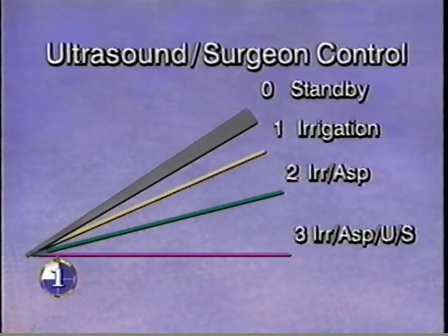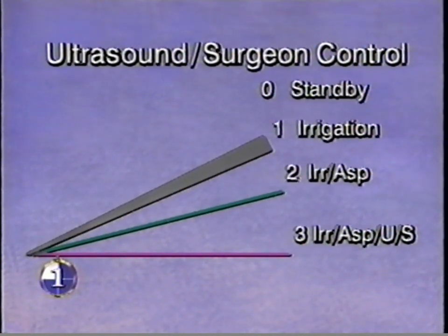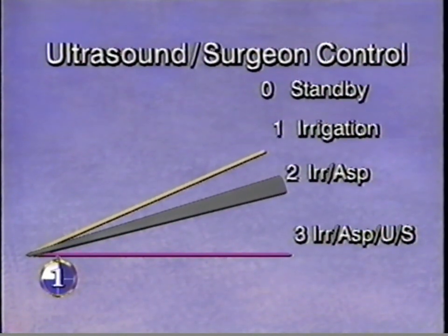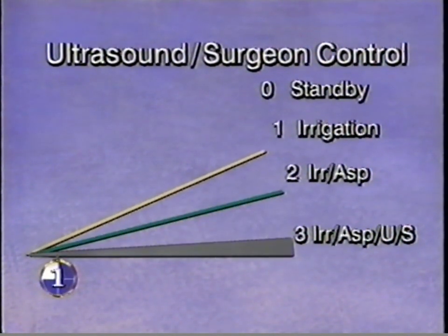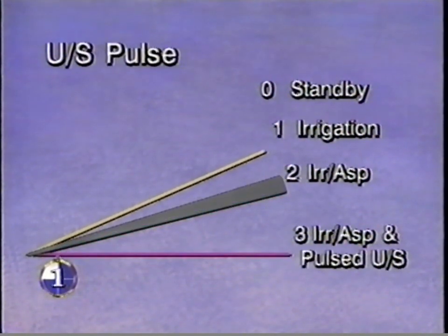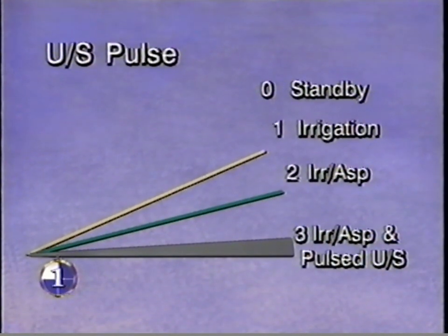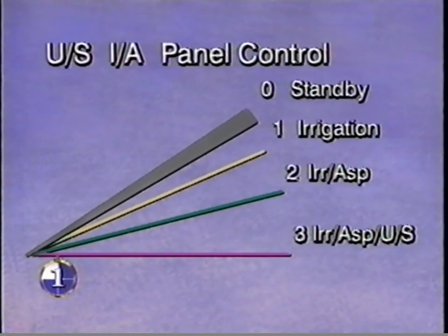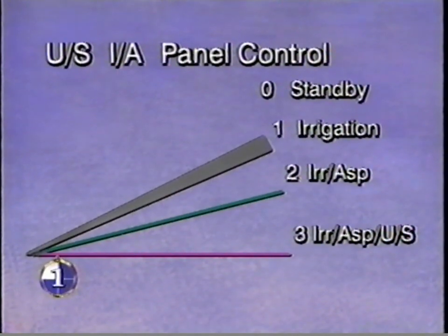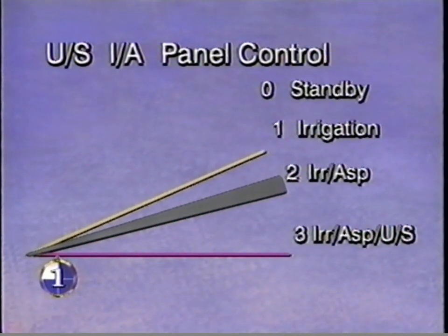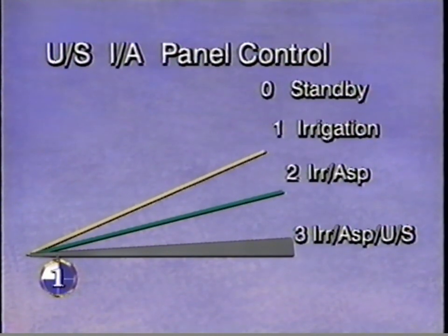If surgeon control is selected in the US phaco or US pulse submodes, position 1 is irrigation. Position 2 is irrigation and aspiration. Position 3 is irrigation and aspiration with linear control of ultrasonics. US pulse position 3 is intermittent linear ultrasonics with fixed aspiration. US IA submode under panel control provides irrigation in position 1, irrigation aspiration in position 2, and simultaneous irrigation, aspiration, and fixed ultrasonics in position 3.